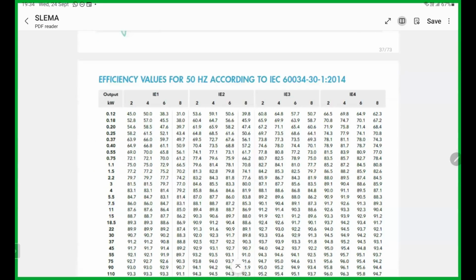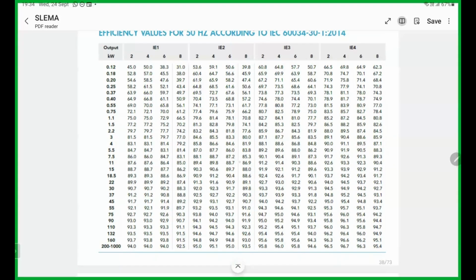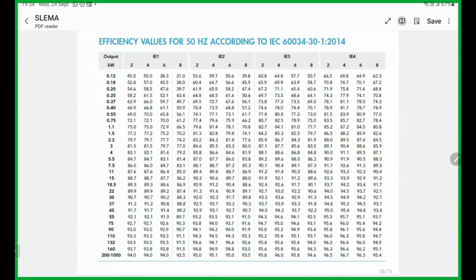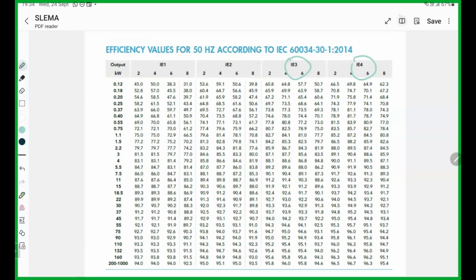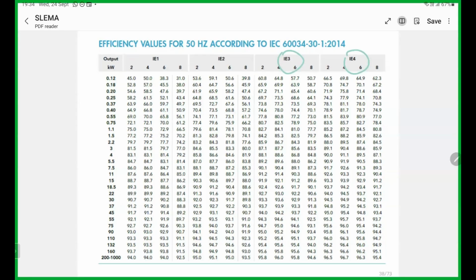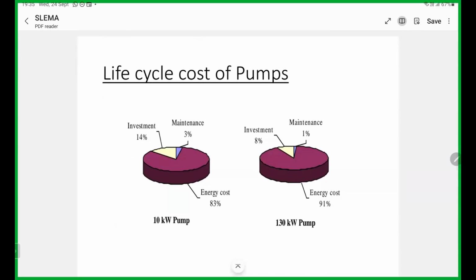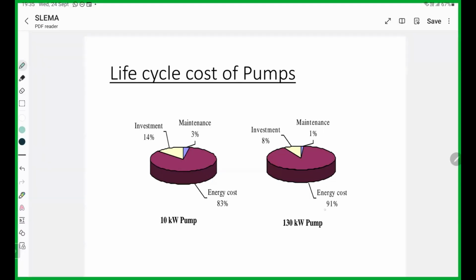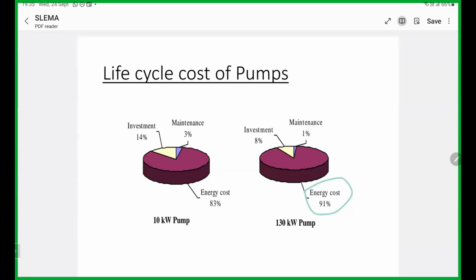If you compare the motor efficiency of IE1, IE3, and IE4, you can see a huge difference here. Definitely we have to go for IE3 or IE4, right? If we think about life cycle cost, that's very important. For a high capacity motor, 91% is from the running cost, right? So energy efficiency is very important when we are going to buy a pump.